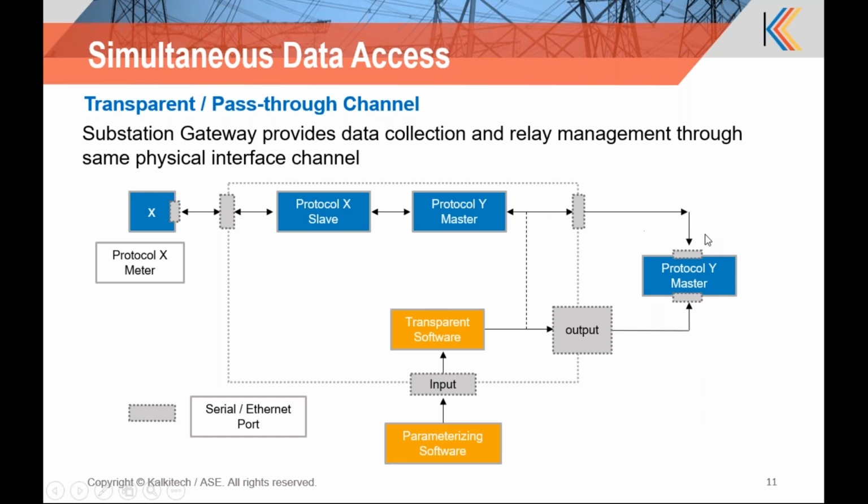This way, using the single port, we will be able to manage live data collection, disturbance record collection, as well as configuration management. If the relay has got two ports, then we can dedicate one for the live data and disturbance and the other for the configuration. So this transparent or pass-through channel is enabling us the simultaneous data access for communication as well as for the configuration.